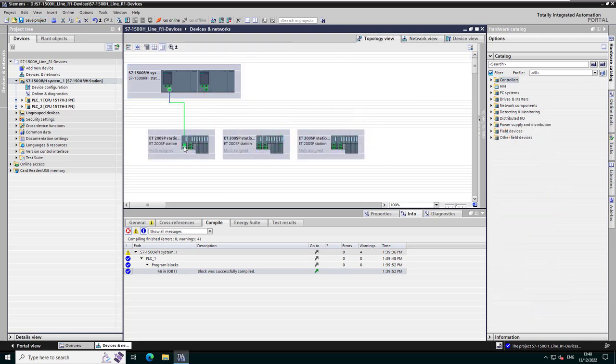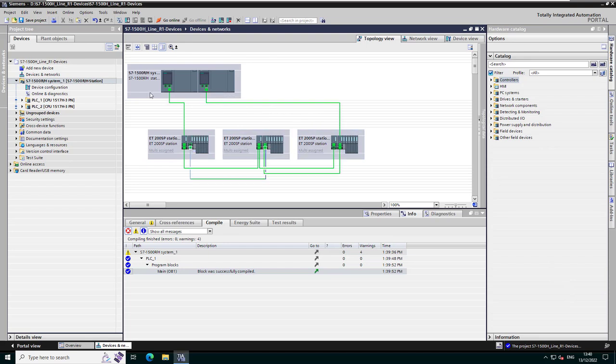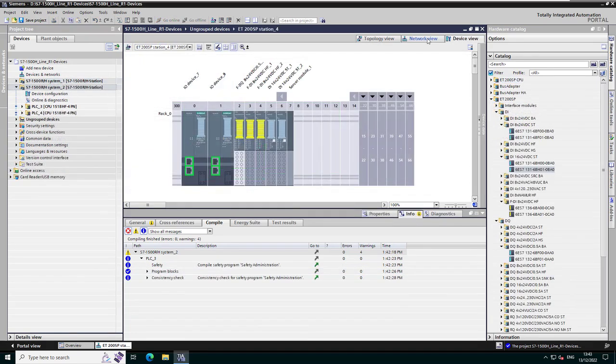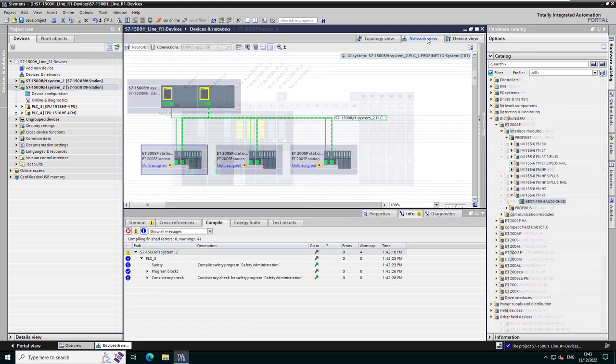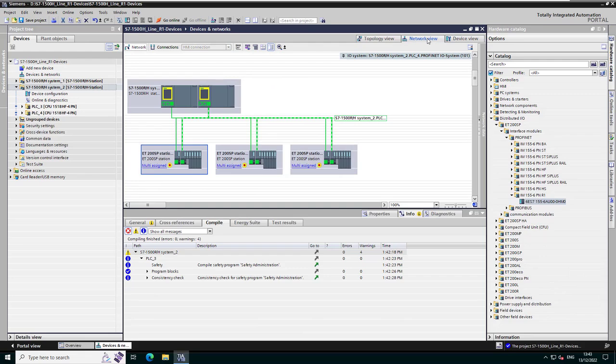The topology configuration is optional, but it will simplify the PROFINET name assignment. Don't forget: with an R1 station, there are two IP addresses and therefore two different PROFINET names per station. To be noted, PROFISAFE modules are supported by ET200SP with interface module R1. Therefore, the line topology with stations R1 can also be used for failsafe applications.